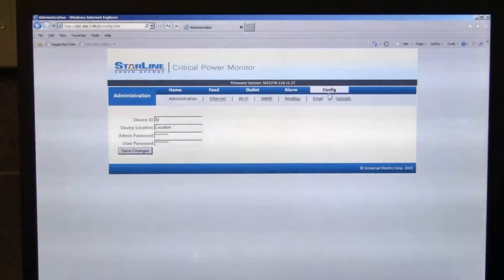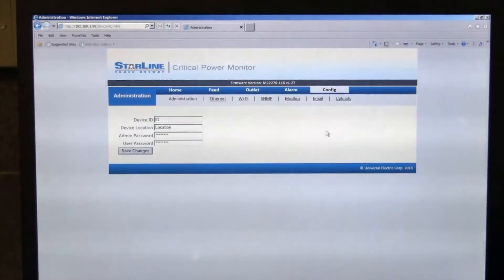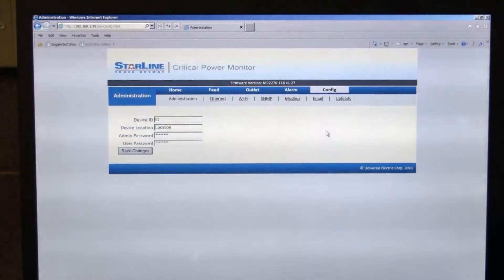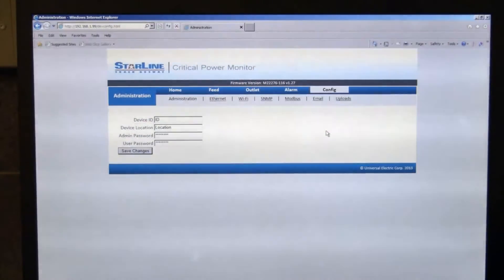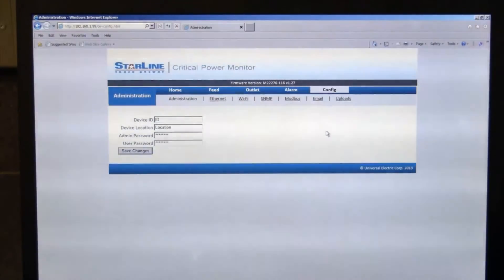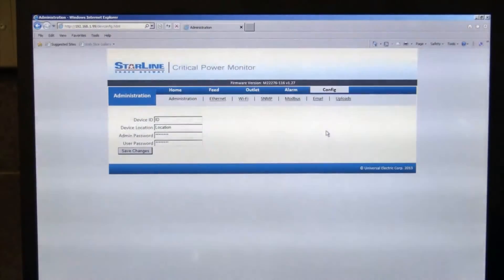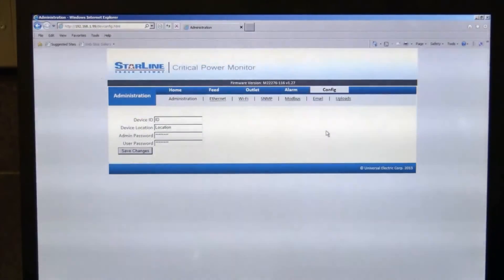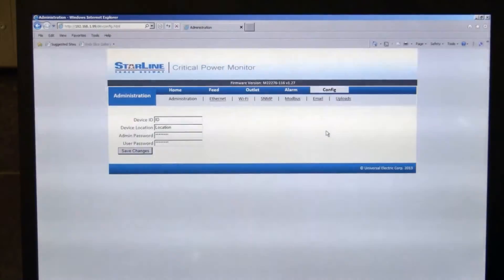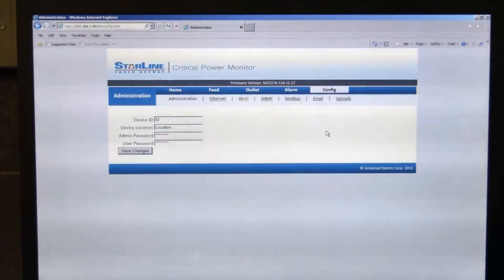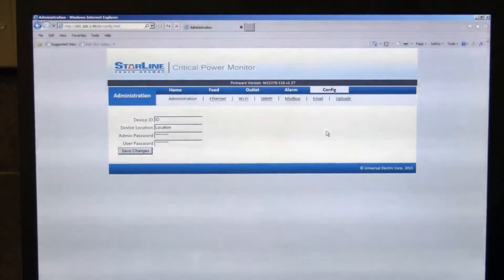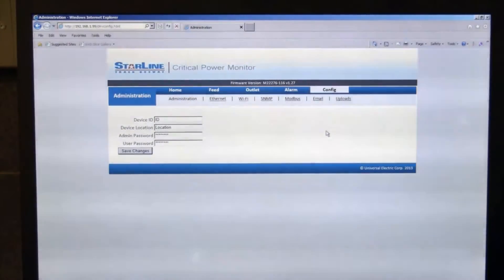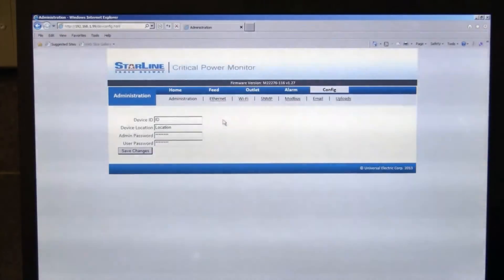Under the configurations tab, you can see some various information that you'll be able to set. So the administration tab under configuration is where you can type in the device ID, device location, and set up your password. By default, the admin and factory user passwords are set to factory, all lower case. You can change those here and then save those settings.